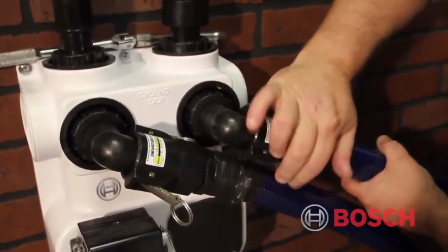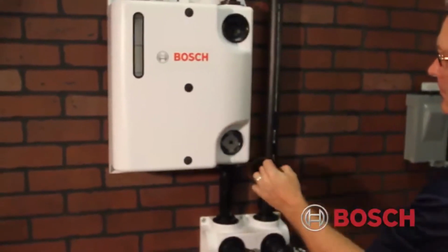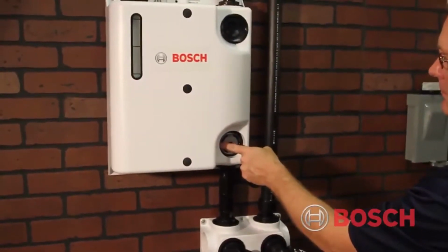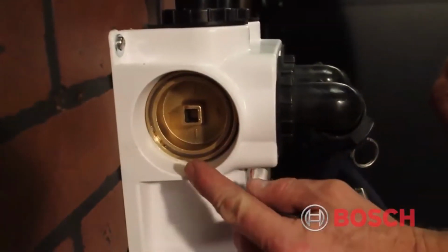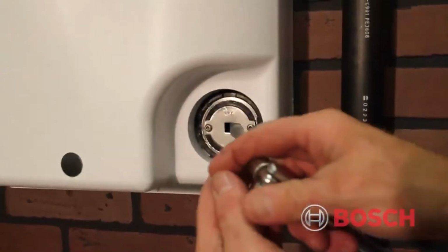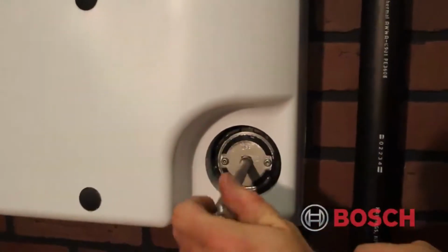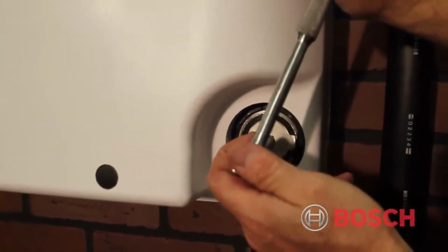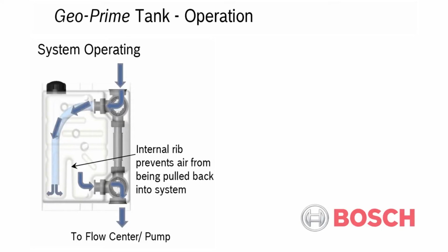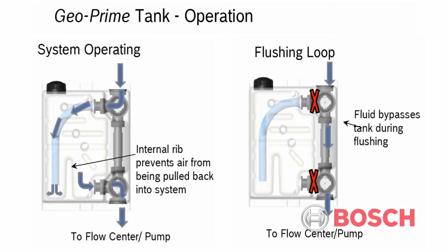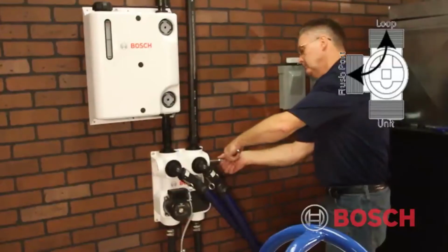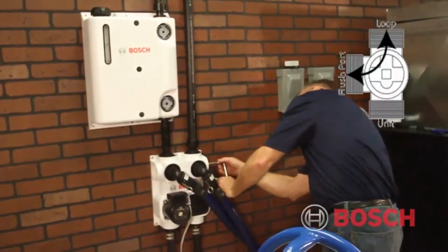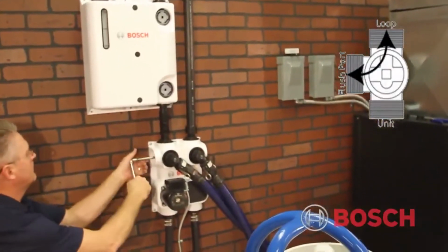In order to properly purge the ground loop, we now have to adjust the position of the factory set 3-way valves on both the Geoprime tank and the flow link pump center. Starting with the Geoprime tank and using a 3/8 inch drive, isolate the prime tank by rotating the 3-way valves from the operation position to the bypass position. Adding any sort of water pressure to the Geoprime tank during commissioning process will void the Geoprime warranty. Next, rotate the flow center 3-way valves so that the off marking is set to the 6 o'clock position, thereby isolating the flow center and the heat pump from the ground loop.